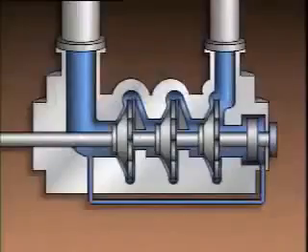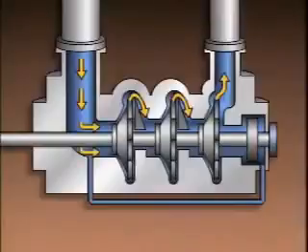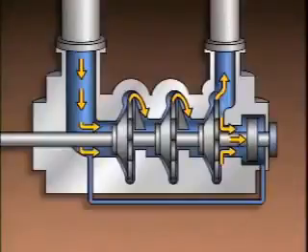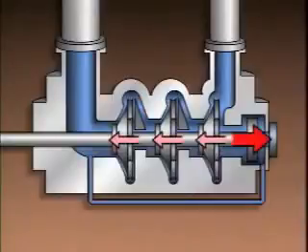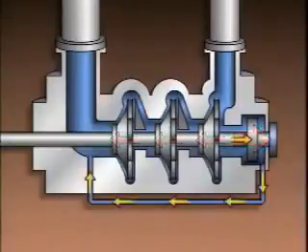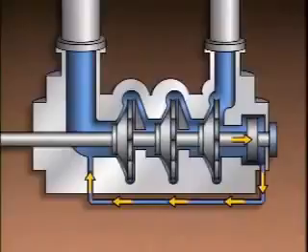On other pumps, the thrust is offset by the arrangement of the impellers. This pump has a balance piston. During operation, some of the fluid leaving the pump flows along the shaft and exerts pressure against the balance piston. That pressure tends to force the pump shaft away from the suction eyes and reduces total thrust. Any fluid that passes by the balance piston is returned to the suction side of the first stage.